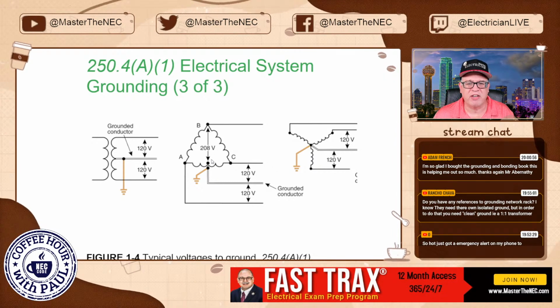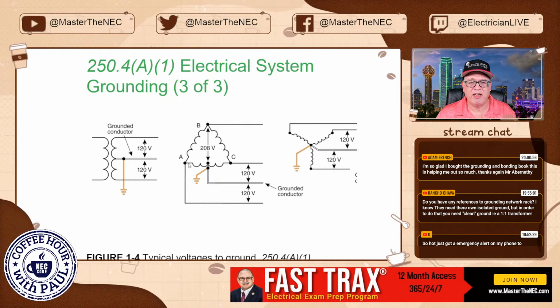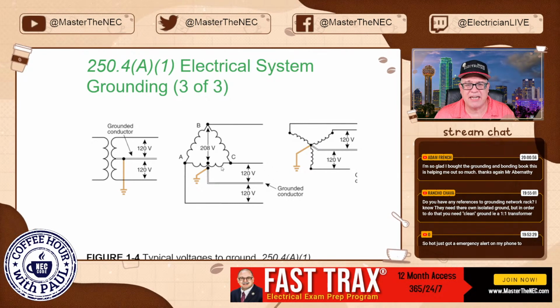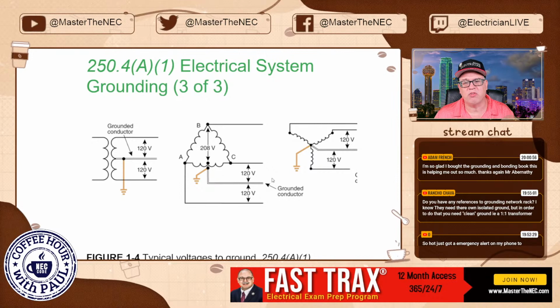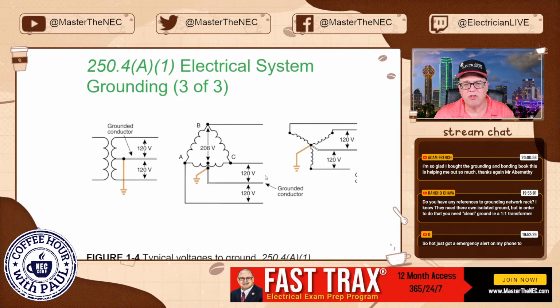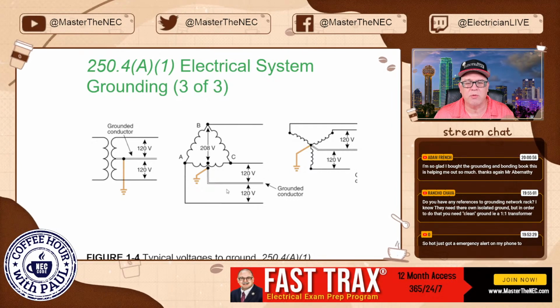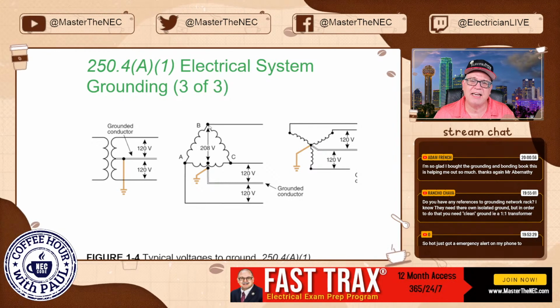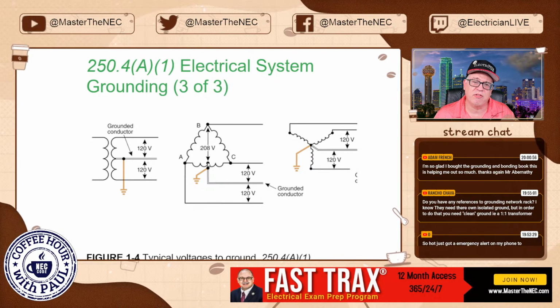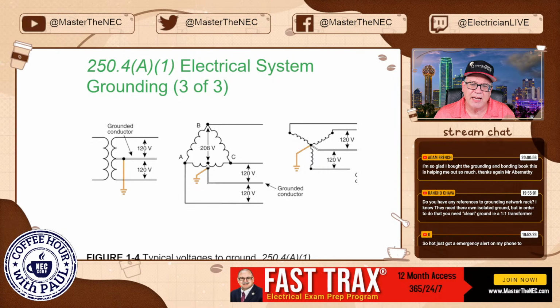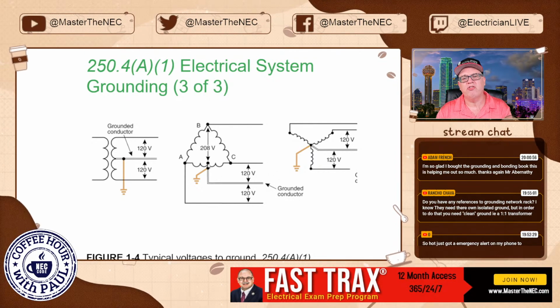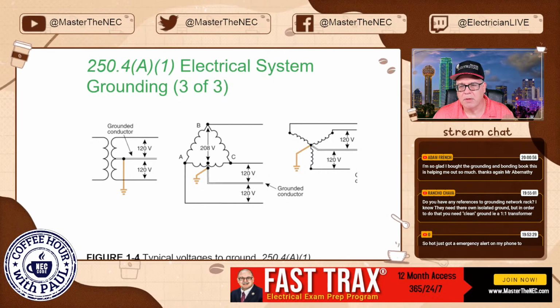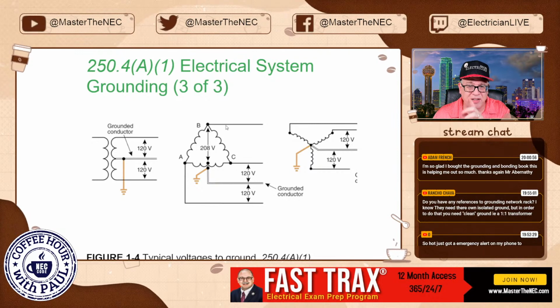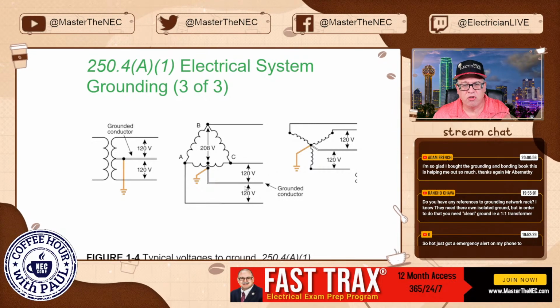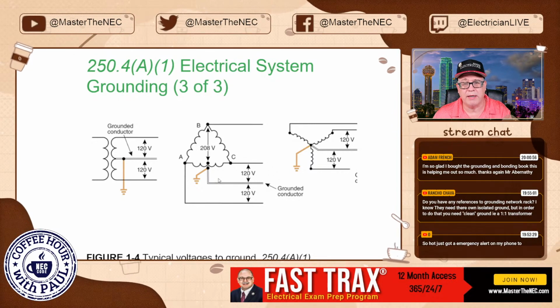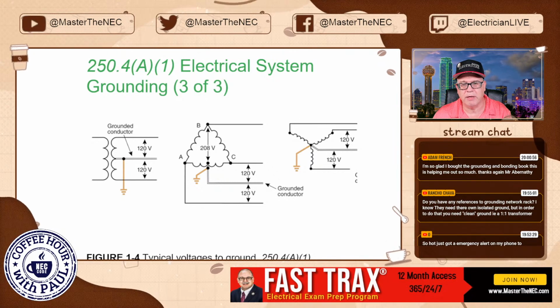So this is a delta high leg, and here's a center tap winding from A to C. And this is how we achieve the 120 and 240. It doesn't show the 240 here, but that's how you would achieve it. And of course, any connection from B leg to this neutral point, vectorially, is going to give you 208 volts, okay? But it's still a grounded conductor because any one of these phases to this grounded conductor is going to give you 120, okay? That type of scenario.